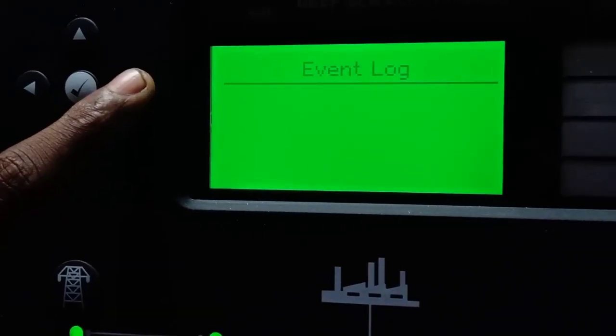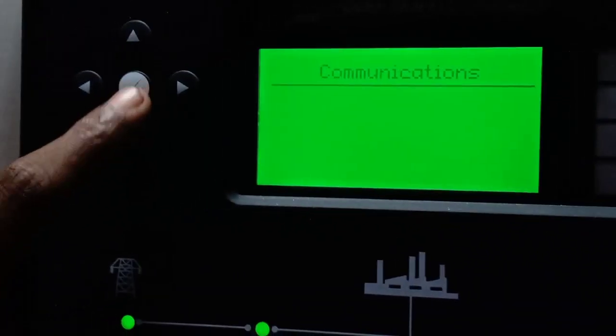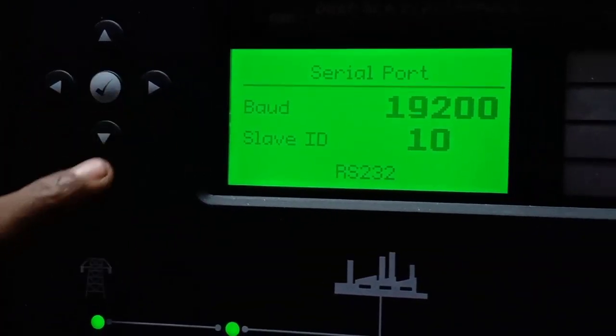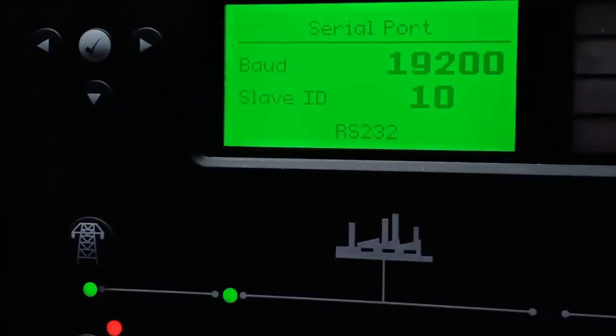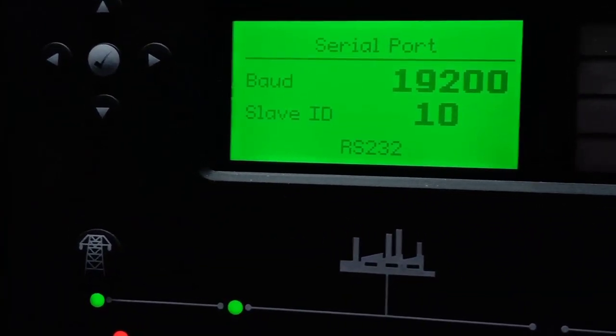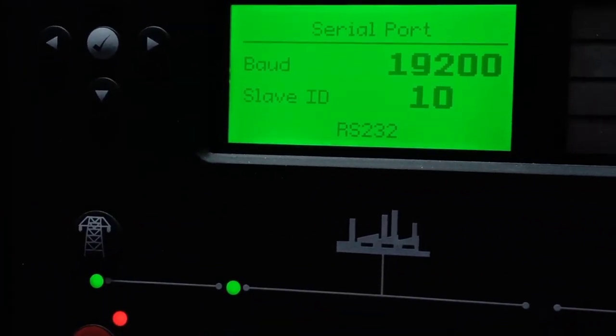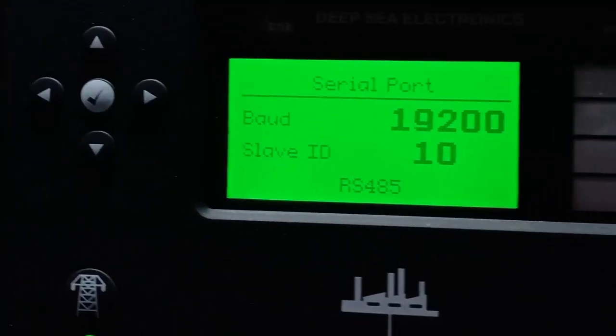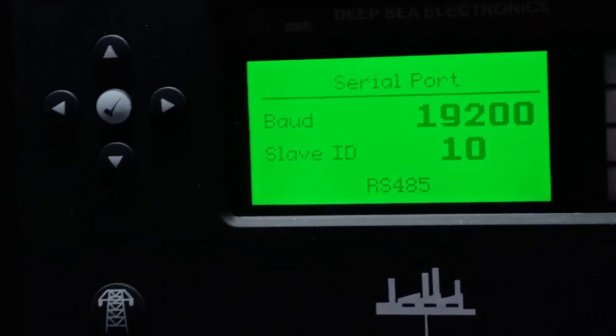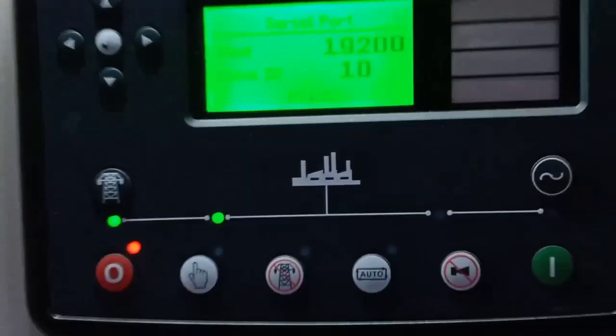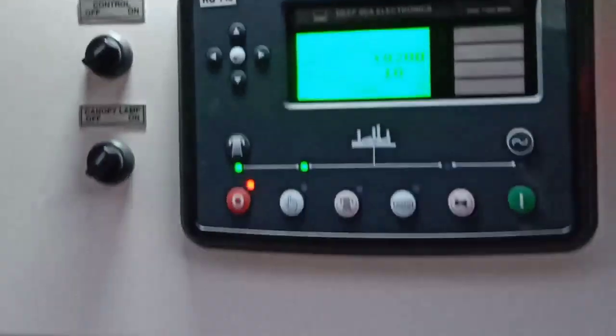To check the settings, press the right arrow key to select the communication settings. Press the down arrow key in communication to check further settings. It shows serial port details, in which the baud rate should be set as 19200. Slave ID should be 10, and these settings are the same for the RS-232 and RS-485 ports. That's all with the controller settings.